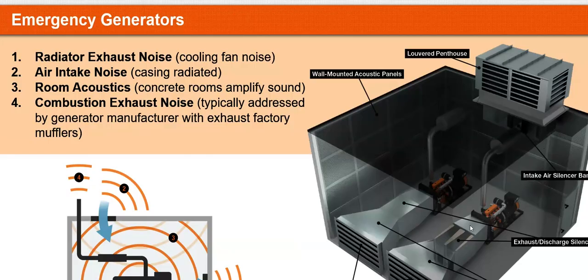You also have your radiator fan, your radiator exhaust to cool off the system. That is typically where you're going to use most of your pressure drop, or the total static this system or this unit can take, mainly because you don't have a lot of room to change the sizing and transition so abruptly into the louvers. So a lot of that available back pressure that you have to play with is going to be used at the radiator exhaust. So just remember that as you're designing solutions for it.